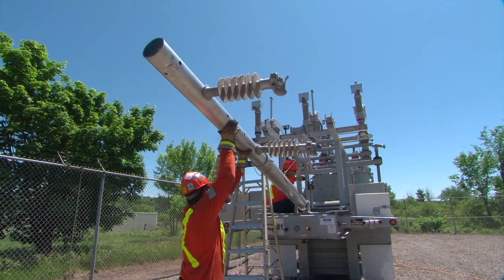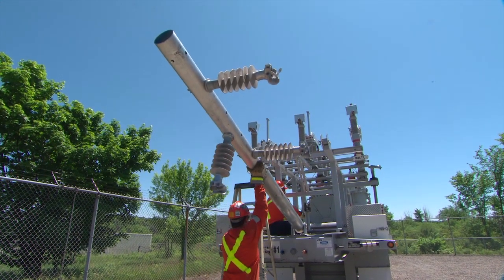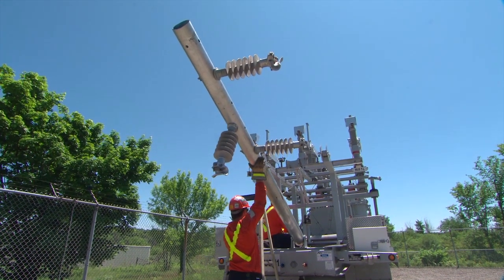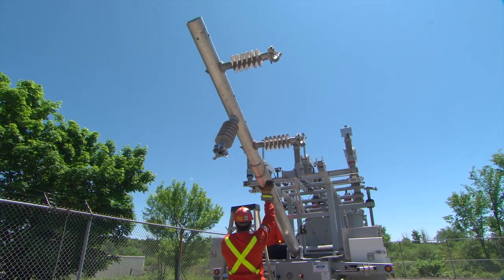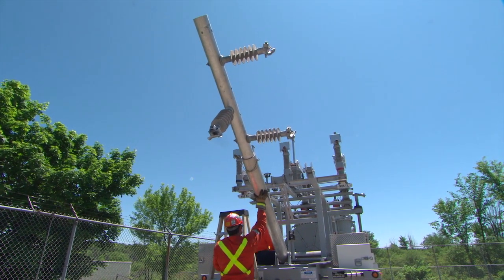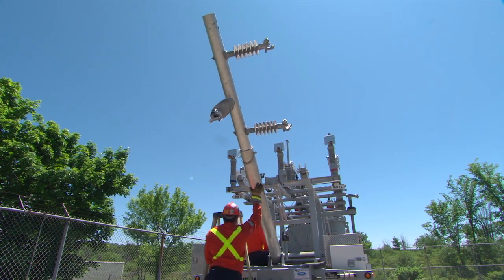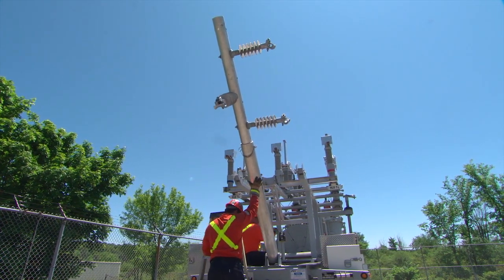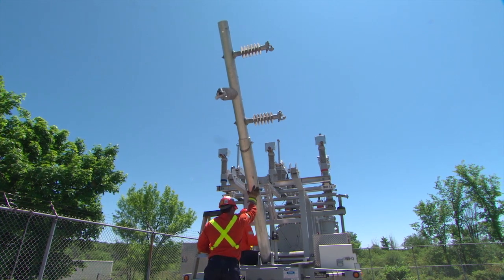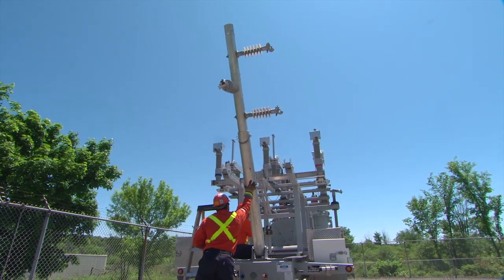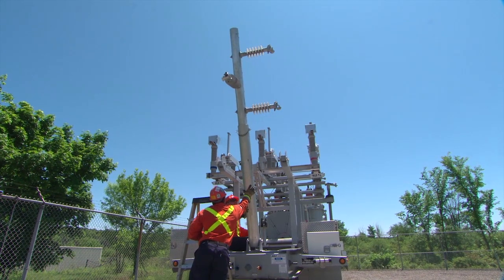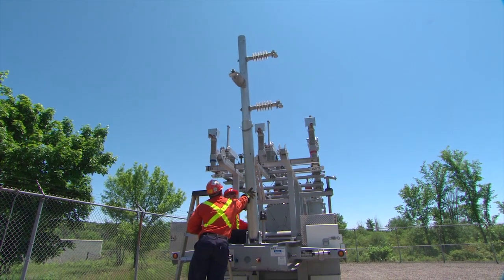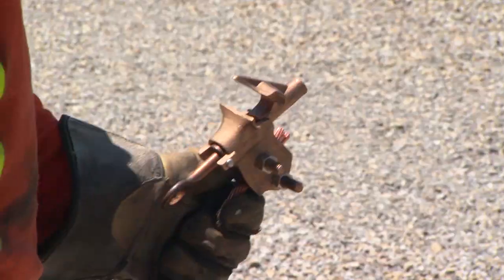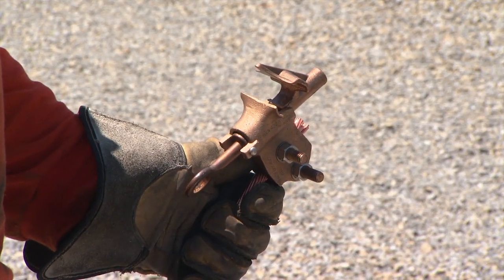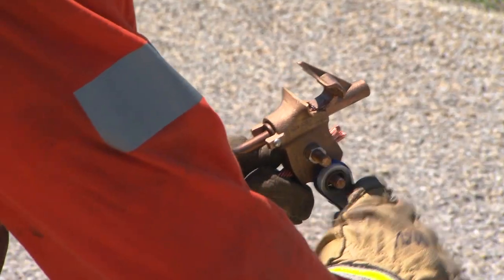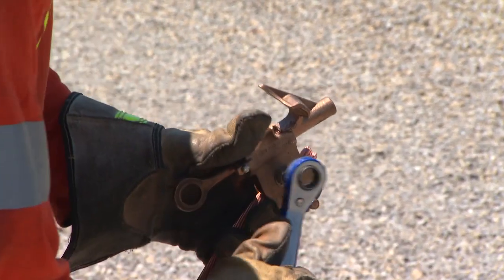If the mobile you are placing in service does not have high-voltage 44 kV cables, then bare conductor must be used for the high-voltage leads. Depending on the station configuration, these leads will either be connected directly from the MUS to the LC-MUS stirrups, or they will be rotated around a mast and then be connected to the LC-MUS stirrups. In either case, the leads must be fabricated and test-fitted while prepping the MUS in order to ensure that the necessary phase-to-phase and phase-to-ground clearances are available for switching.